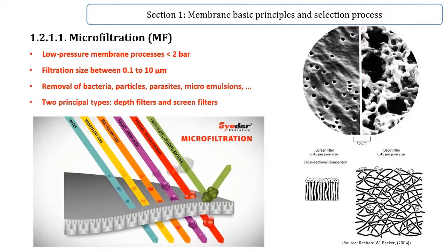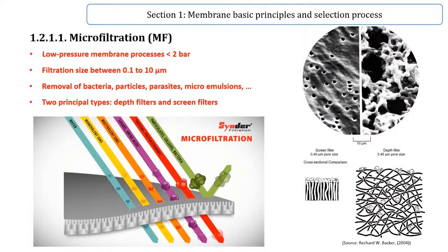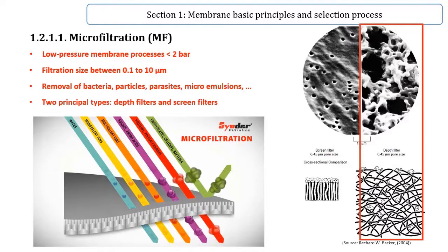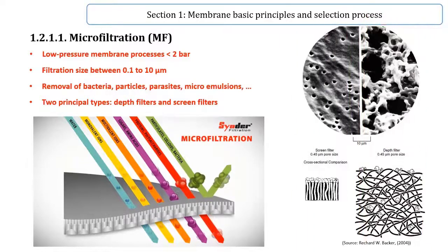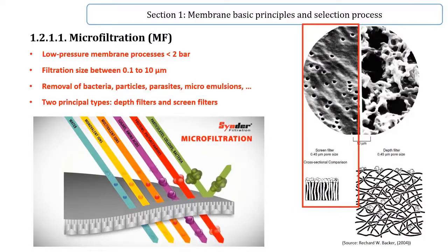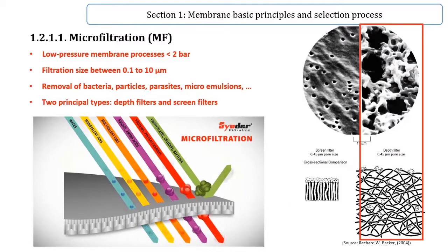Screen filter membranes rapidly become clogged by the accumulation of retained particles at the top surface. Depth filters have a much larger surface area available for the collection of particles, providing a larger holding capacity before fouling. Screen membrane filters are preferred for cross-flow microfiltration systems, but depth filters are usually preferred for dead-end operating mode.